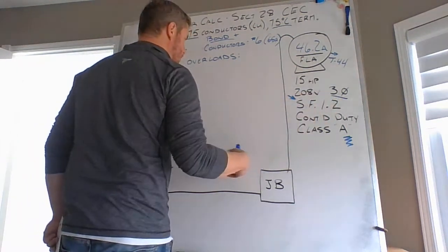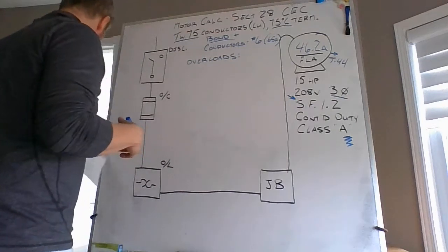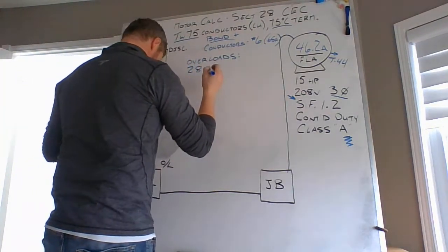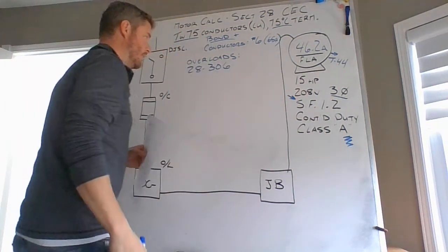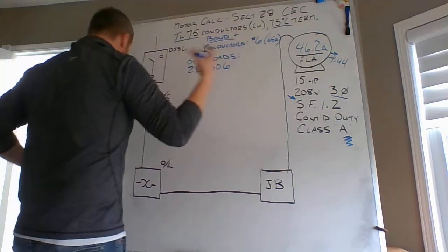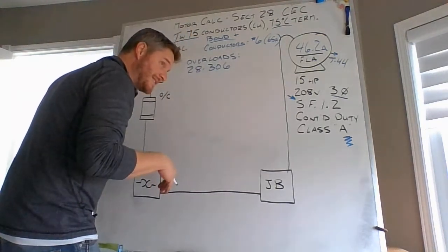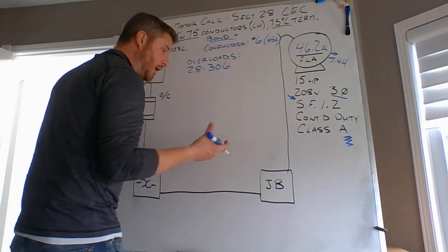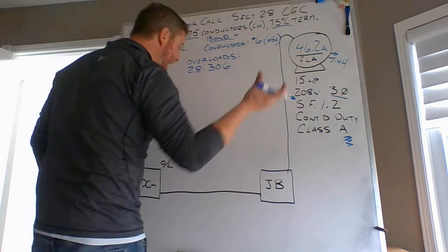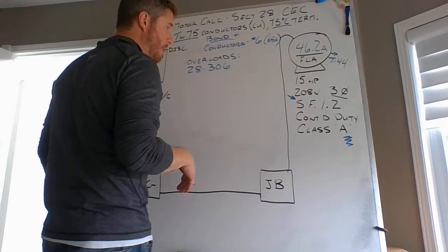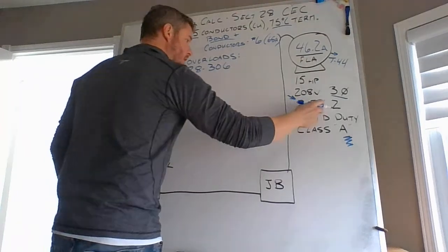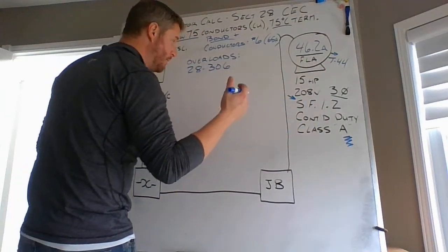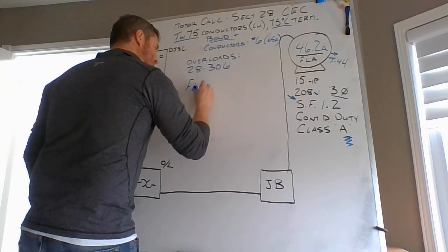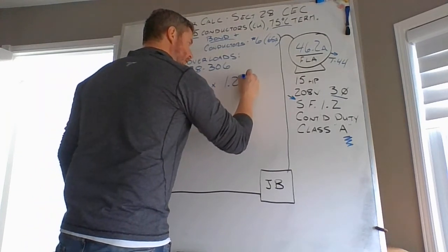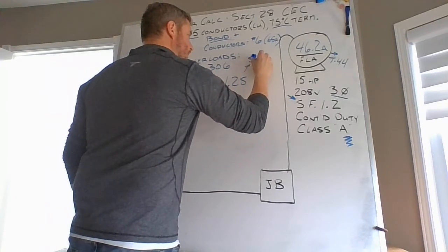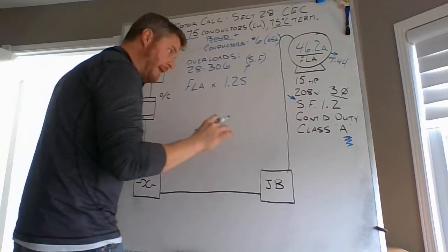If I have a service factor of 1.2, my multiplier comes from 28-306, Section 28, Rule 306. And that says that if it's going to be a service factor of 1.15 or less than 1.15, or it's not marked, then your multiplier is 1.15. But if it's 1.15 and greater, then it has a multiplier of 1.25. So in this circumstance, my service factor is marked at 1.2, which would be 1.15 or greater. So I almost have exactly the same calculation. Again, I take my FLA and I multiply that by 1.25, and that's because of my service factor. It's stamped on the nameplate that it's 1.2.